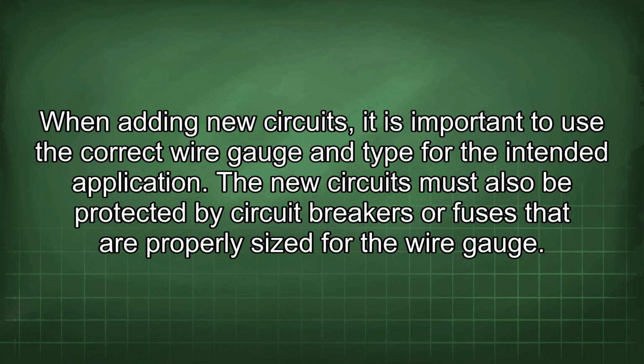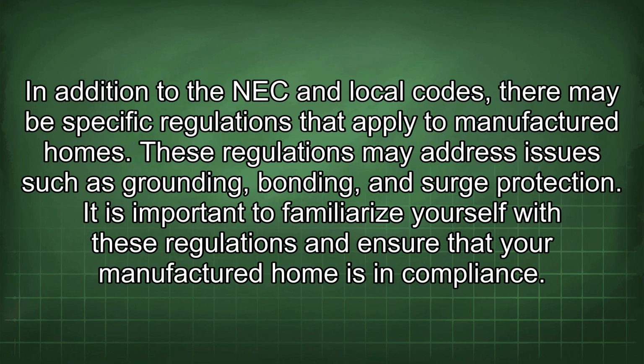When adding new circuits, it is important to use the correct wire gauge and type for the intended application. The new circuits must also be protected by circuit breakers or fuses that are properly sized for the wire gauge. In addition to the NEC and local codes, there may be specific regulations that apply to manufactured homes. These regulations may address issues such as grounding, bonding, and surge protection. It is important to familiarize yourself with these regulations and ensure that your manufactured home is in compliance.